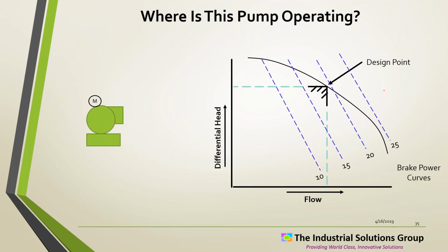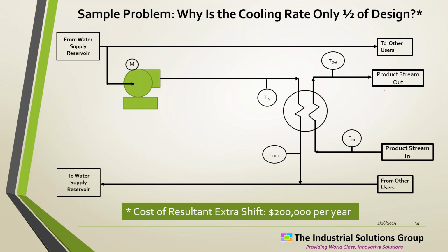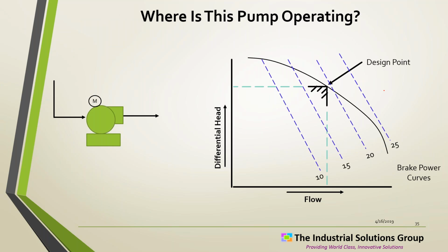And the other important thing to talk about here is they were coming off of a reservoir. So that's a pressurized supply pump. So this is a booster pump. This isn't coming directly from the water source. We started looking at it, pulled the pump curve and said, yep, this is where we wanted to design. Because the temperatures on the heat exchanger looked okay, we thought we were probably okay there, but we were really focusing on the pump.